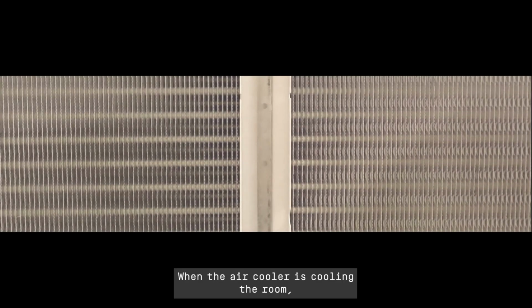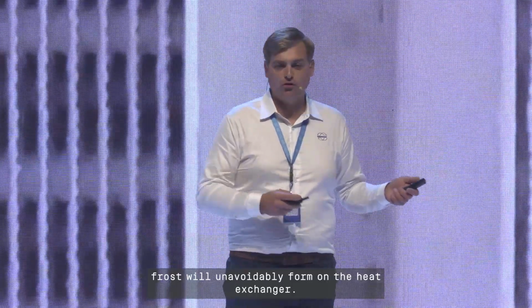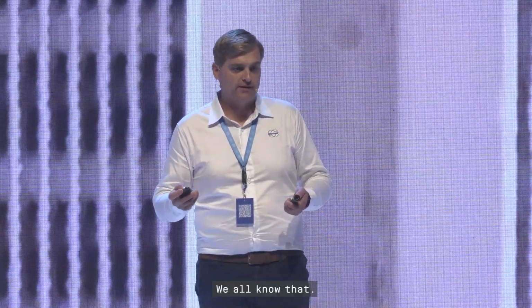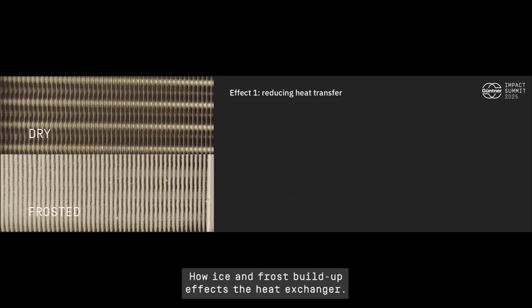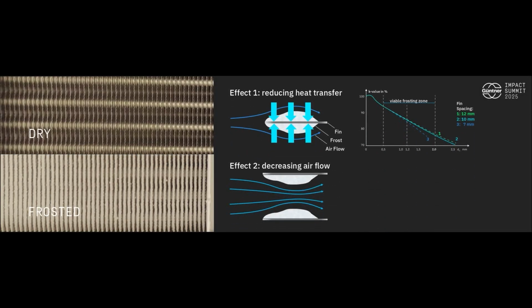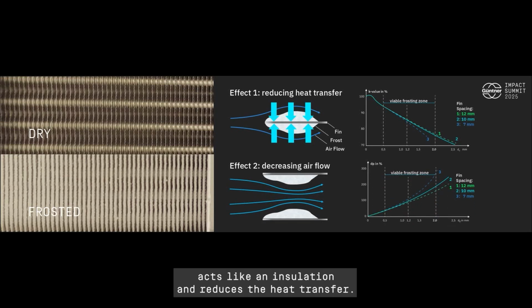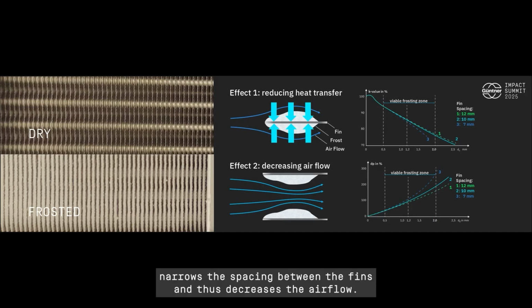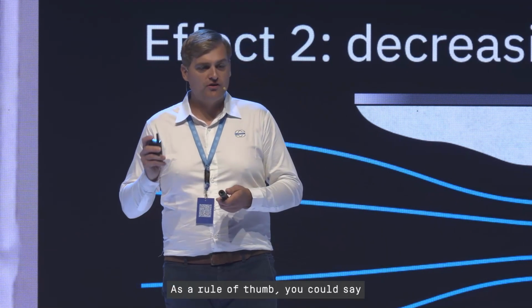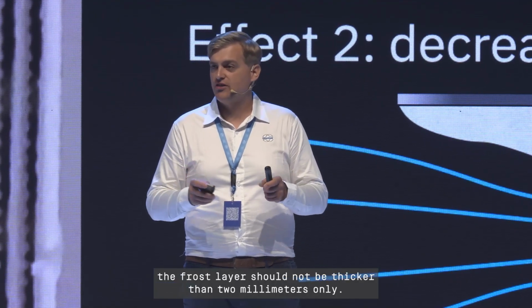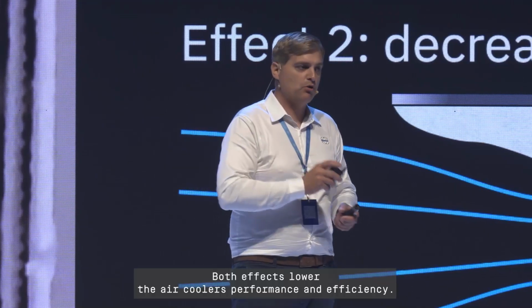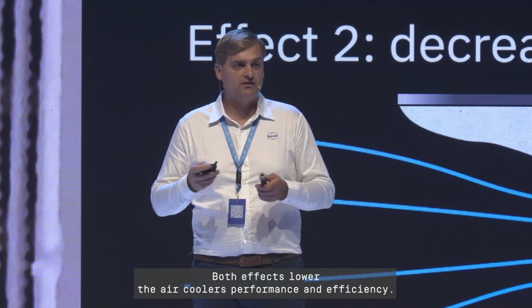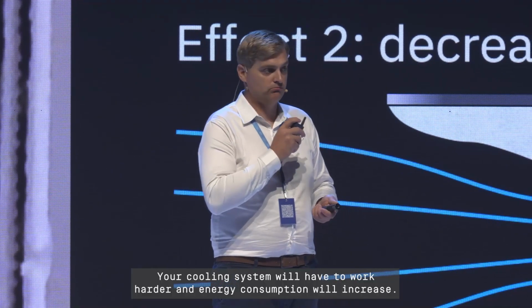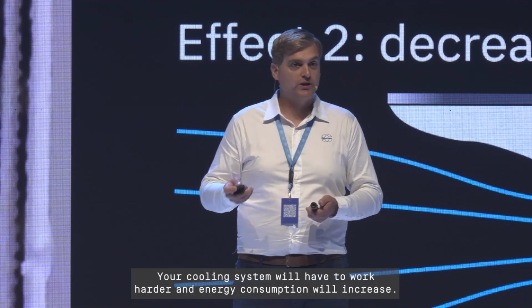When an air cooler is cooling the room, frost will unavoidably form on the heat exchanger. We all know that. Let's have a closer look at how ice and frost build-up affects the heat exchanger. First, a frost layer acts like an insulation and reduces the heat transfer. Second, the frost build-up narrows the spacing between the fins and thus decreases the airflow. As a rule of thumb, the frost layer should not be thicker than 2 millimeters. Both effects lower the air cooler's performance and efficiency - your cooling system will have to work harder, and energy consumption will increase.